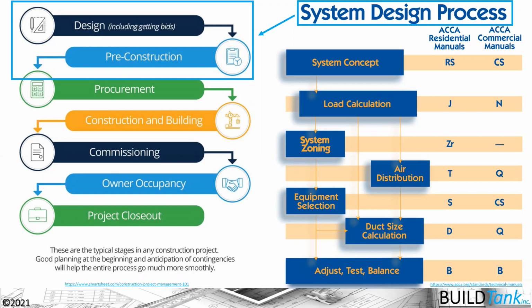So we have two situations that ultimately get created. One is that the HVAC designer is going to assume that everything that is specified is going to be executed perfectly, and they'll do a completely right-sized calculation for the house. And what happens if that isn't the case? Or that HVAC contractor is going to assume that the specifications and construction aren't going to go absolutely perfectly, and they're going to make some adjustments to their design to ensure that they're not going to get a lot of callbacks for comfort and whatnot, which tends to oversize the equipment or potentially undersize the equipment.